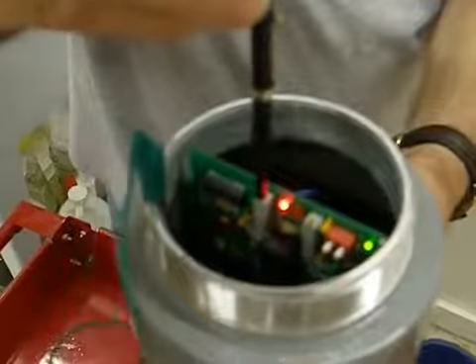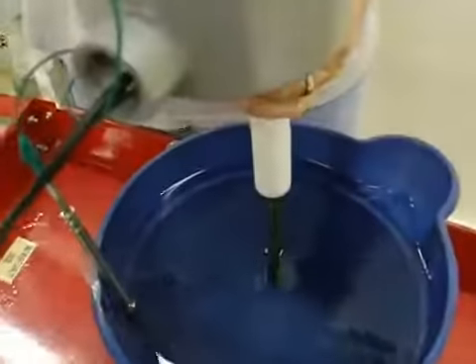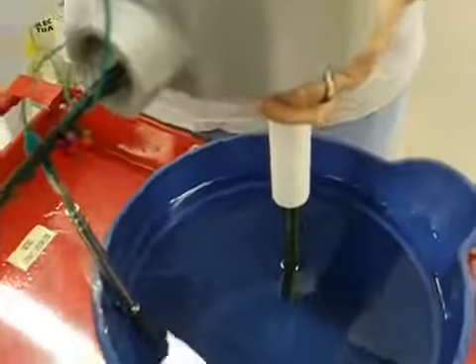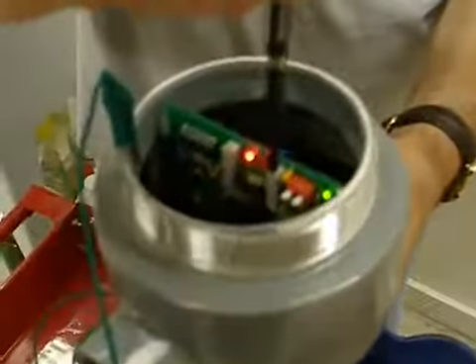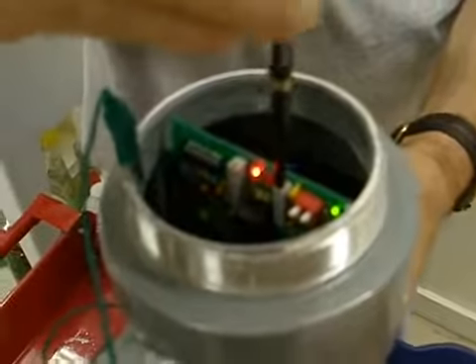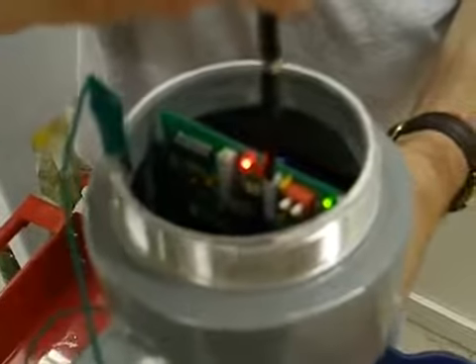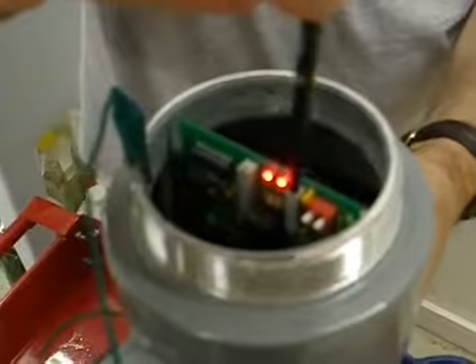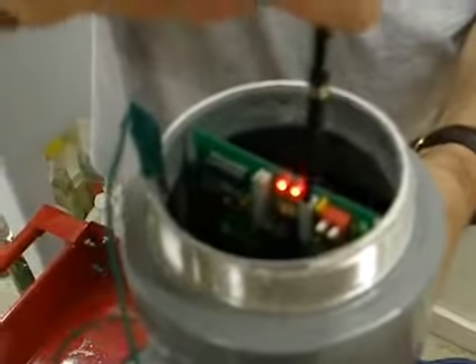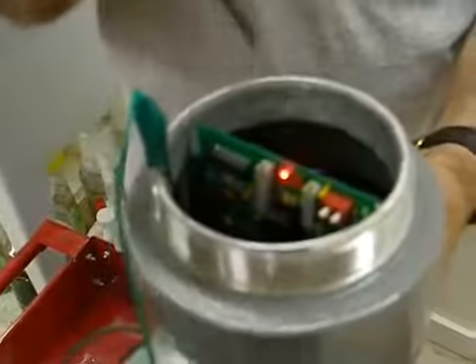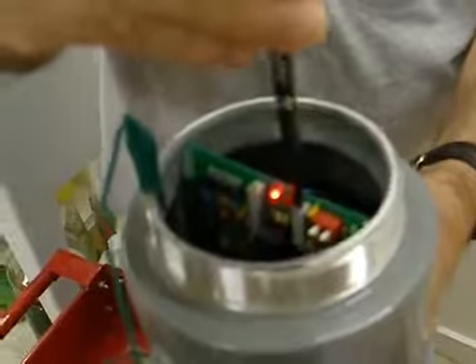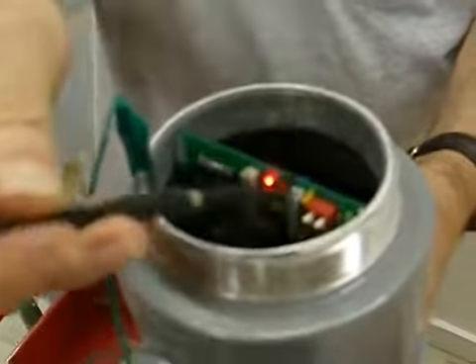Now I'm going to dip it another inch in the water. This is the high set point. I'm going to turn the high set point clockwise until it just comes on. Turn it off, on, and you can see, well, I'm wiggling around here, but I'm going to try to be stable.